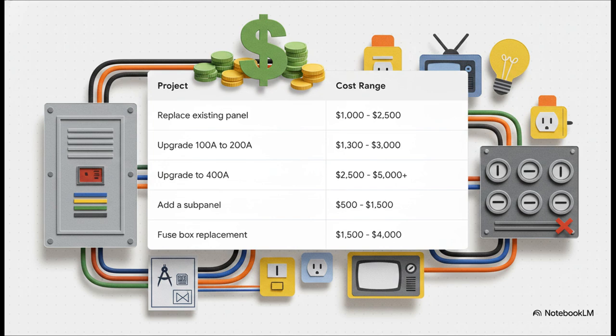Of course, upgrading your capacity does come with a price tag. Let's walk through the realistic costs. If you're doing a simple like-for-like replacement, say just swapping out an old 200-amp panel for a brand new one, you're looking at between $1,000 and $2,500. Bumping an old 100-amp service up to that modern 200-amp standard, that usually runs from $1,300 to $3,000.